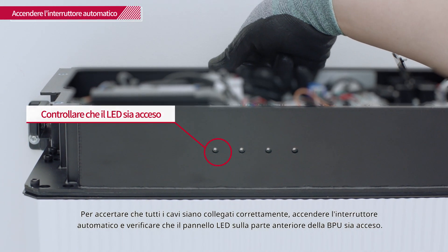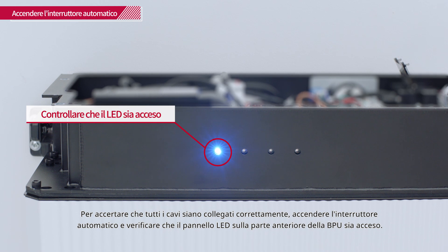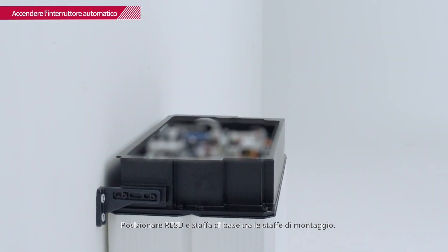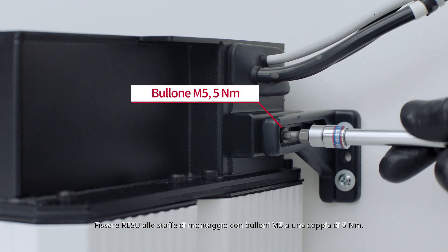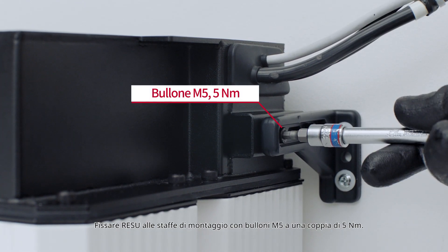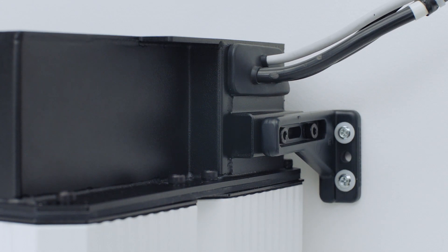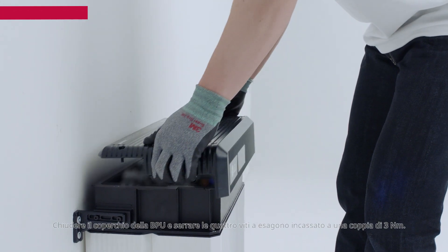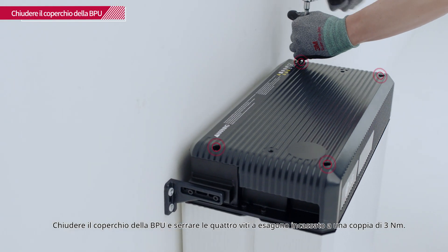To ensure that all the cables are properly connected, turn on the circuit breaker and check that the LED panel on the front of the BPU is on. Place the RESU and base bracket between the mounting brackets and fix the RESU to the mounting brackets with M5 bolts with a torque of 5 Nm. Close the BPU cover and tighten the 4 hex socket screws with a torque of 3 Nm.